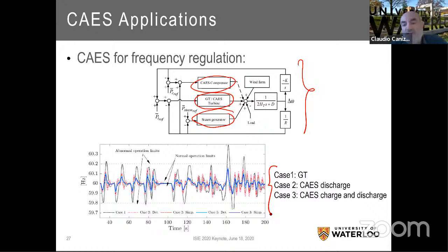So what you have here is the system where you have a gas turbine, okay, as indicated here, which provides certain frequency regulation, but it falls outside the bandwidth set by the ISO in Ontario. Okay. The gas turbine is not fast enough, is not able to provide the required services.